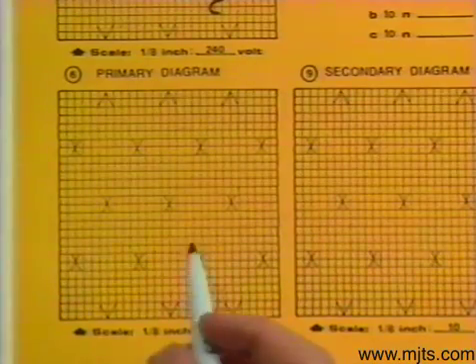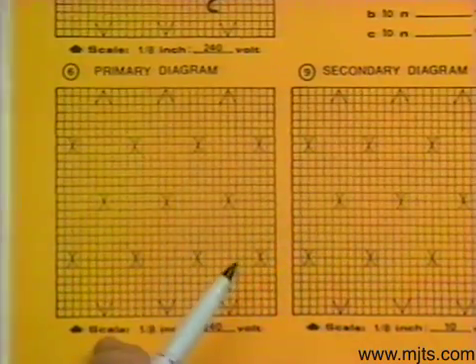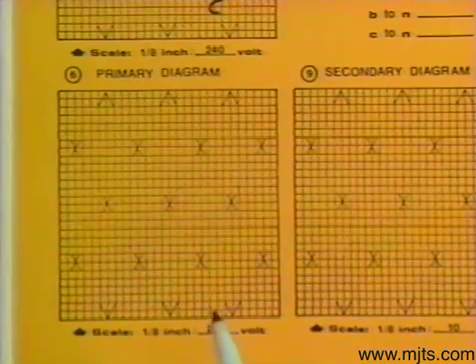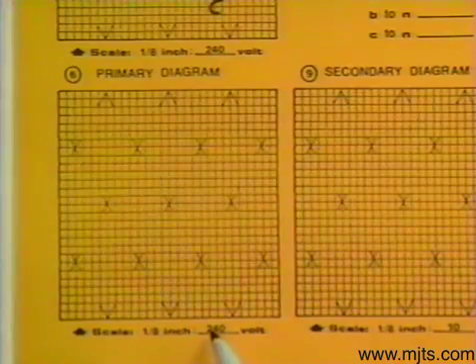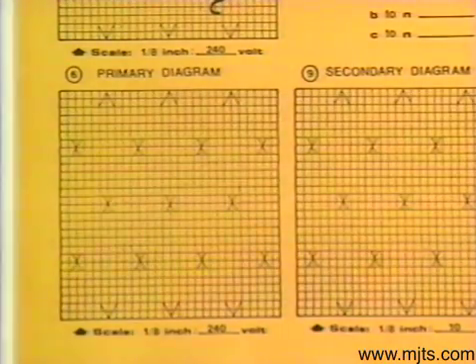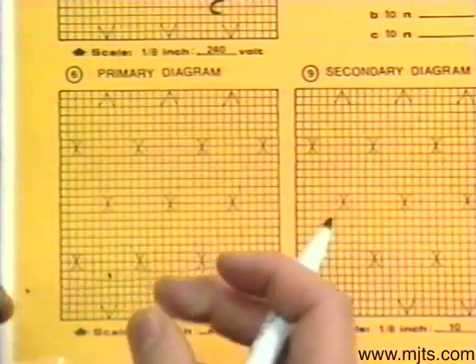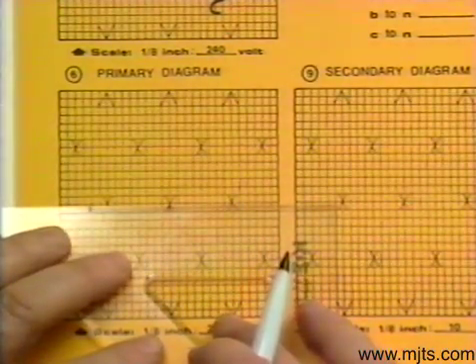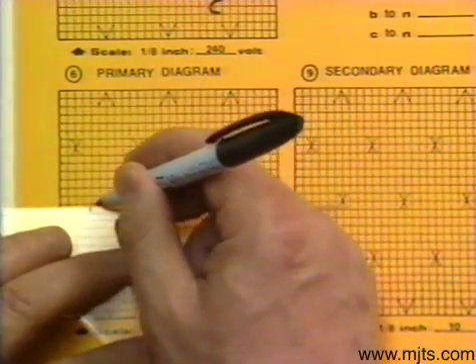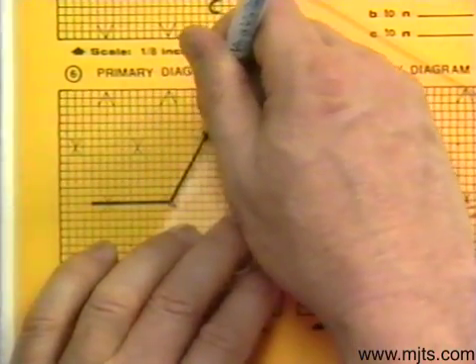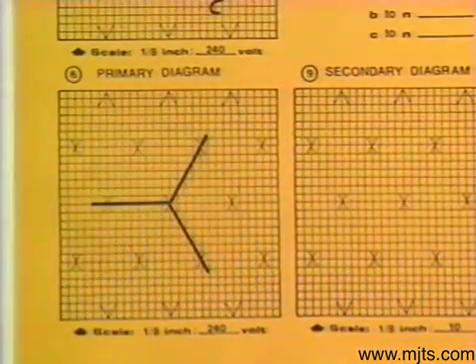Step six: on our primary diagram we want a Y connection to satisfy the voltage on the high side. The coil voltage is 2400 volts, so taking 240 into 2400 gives us 10 eighths, or one and a quarter inches. We draw vectors to scale. For a YY connection, we use a different procedure when labeling for polarity — uppercase letters A, B, and C for our phases on the high side.